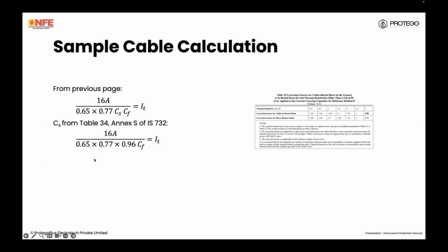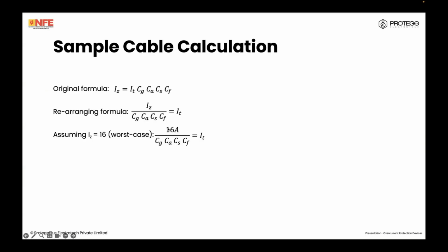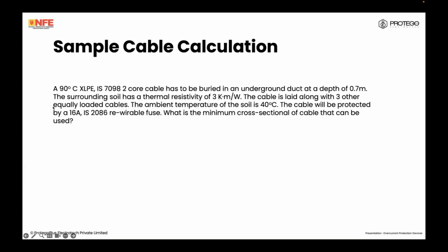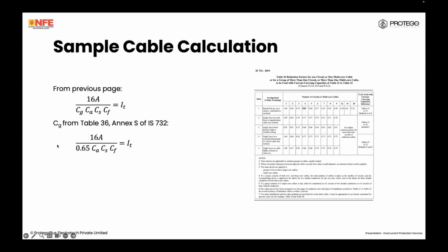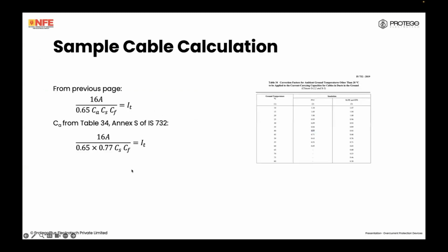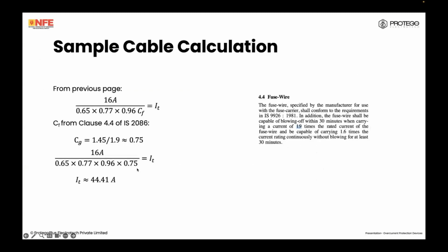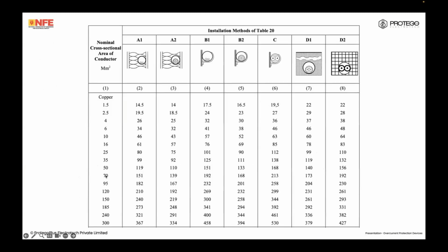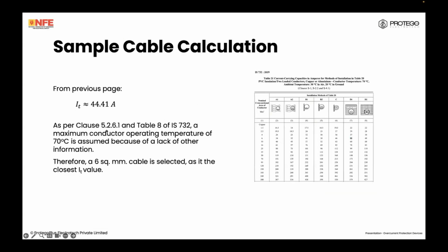So you see, for a circuit, the traditional mindset is to choose something that will just carry more than 16 amps as the load current. We actually need a cable that can carry 44.41 amps. So where normally an electrician would have specified 2.5 square mm, for reference method D1, you can see you actually need a 6 square mm cable. So that is where the derating comes in. So therefore, we take a 6 square mm value.